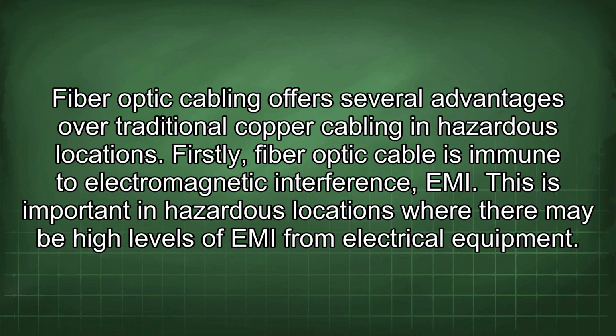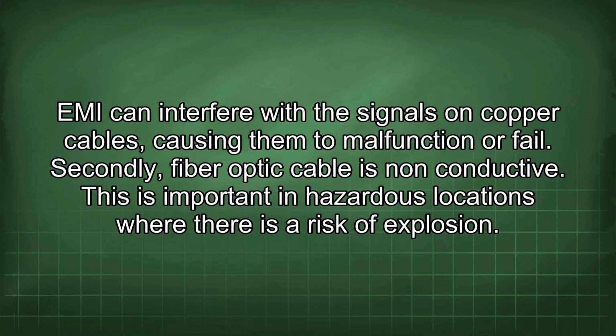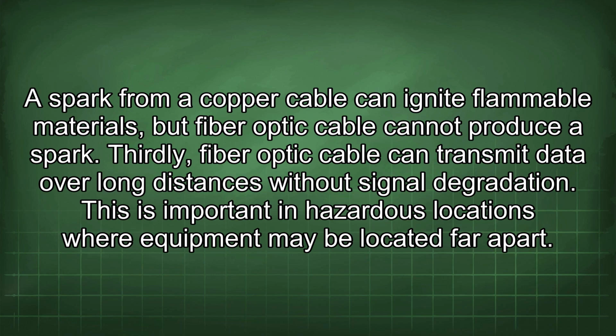Fiber optic cabling offers several advantages over traditional copper cabling in hazardous locations. Firstly, fiber optic cable is immune to electromagnetic interference (EMI). This is important in hazardous locations where there may be high levels of EMI from electrical equipment. EMI can interfere with the signals on copper cables, causing them to malfunction or fail. Secondly, fiber optic cable is non-conductive. This is important in hazardous locations where there is a risk of explosion. A spark from a copper cable can ignite flammable materials, but fiber optic cable cannot produce a spark. Thirdly, fiber optic cable can transmit data over long distances without signal degradation. This is important in hazardous locations where equipment may be located far apart.